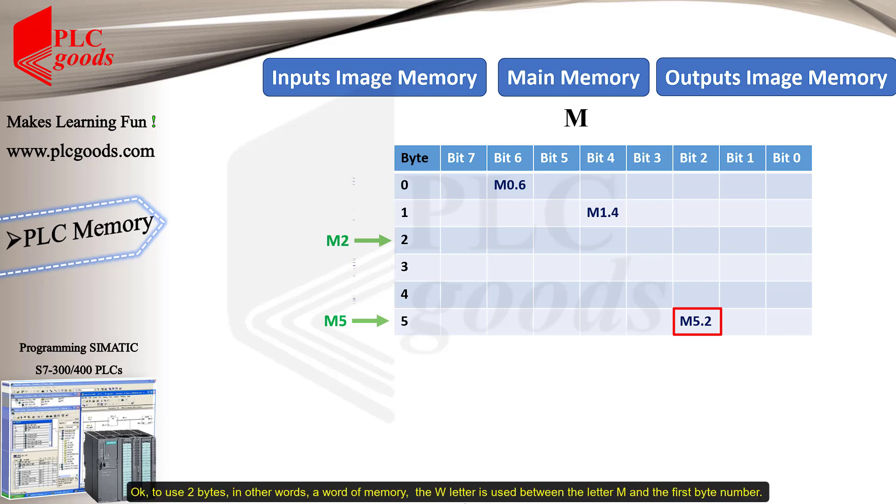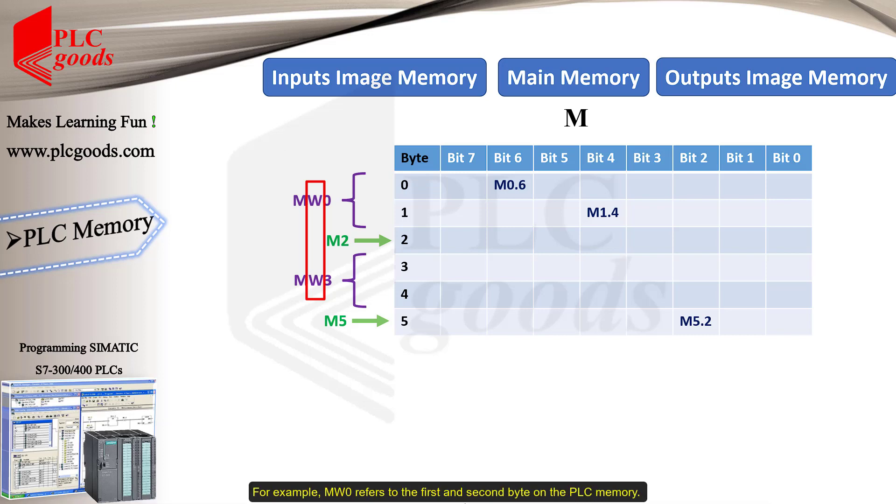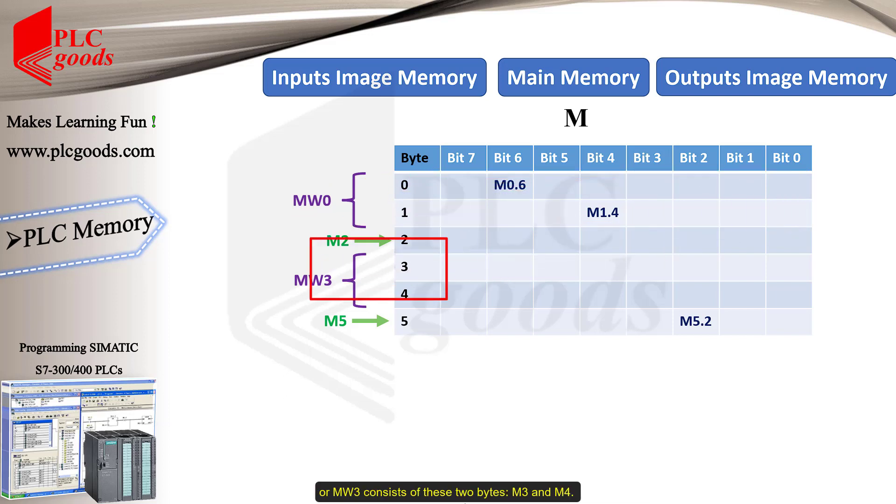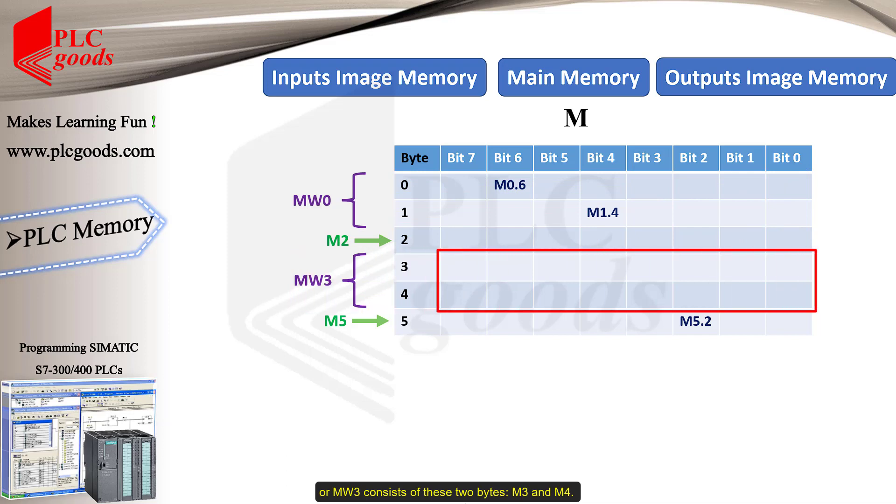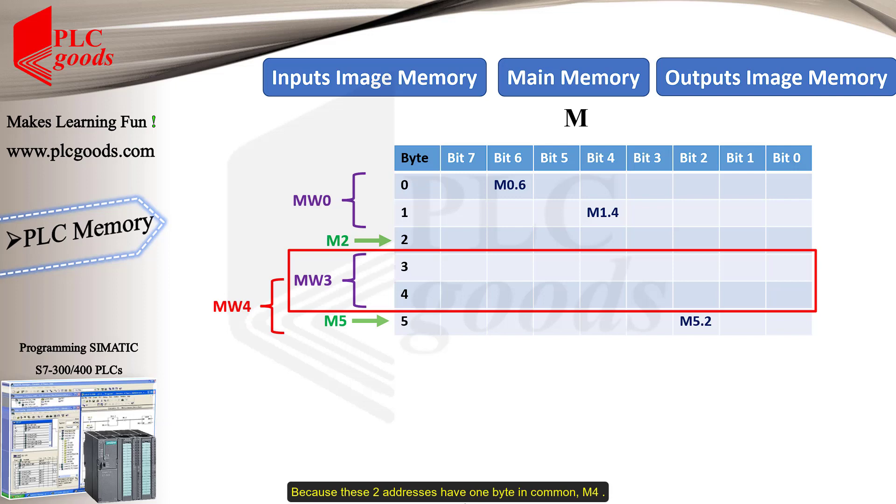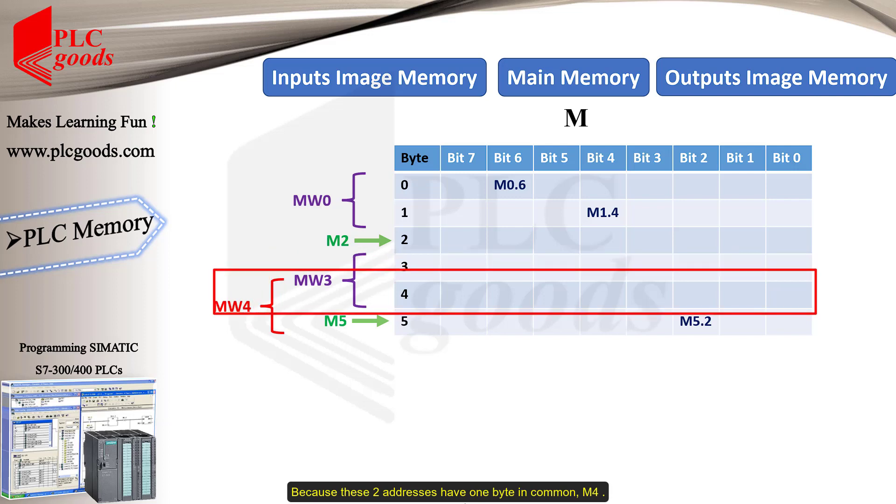Okay, to use two bytes, in other words, a word of memory, the W letter is used between the letter M and the first byte number. For example, MW0 refers to the first and second byte on the PLC memory. Or, MW3 consists of these two bytes, M3 and M4. Hey, attention! If we use MW3 to store a number, we shouldn't use MW4 to store another number, because these two addresses have one byte in common, M4.